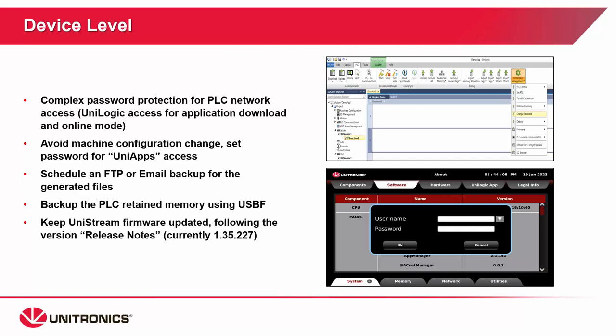If the UniStream will be generating any files, it's recommended to set up or schedule FTP or email backups of those generated files — that way you're not relying on local storage and all that information will be backed up. Upon commissioning of a device, if you are using retained tags, it's recommended that you back up those retained tags to a USBF file. This can be done in UniApps or from UniLogic. This way, if the PLC memory is ever compromised, you can reload the retained tags from the USBF file instead of reentering everything manually.